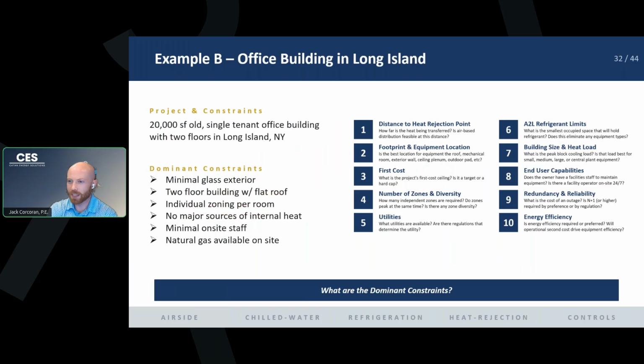Our next example B is an office building in Long Island, right? We've got a 20,000 square foot old single tenant office building, and it's 2 stories. So dominant constraints: it's an older building, right? We don't have as much glass exterior like in these modern buildings. We're going to have 2 floors this time and a flat roof. Since it's an office, there's going to be a bunch of individual rooms. There are no major sources of internal heat. It's a single tenant that maybe is not some mega conglomerate corporation. They're just a small growing business. There's no one on site that handles facilities, but they do have natural gas available since it's an old existing building, and they got grandfathered in with the gas.